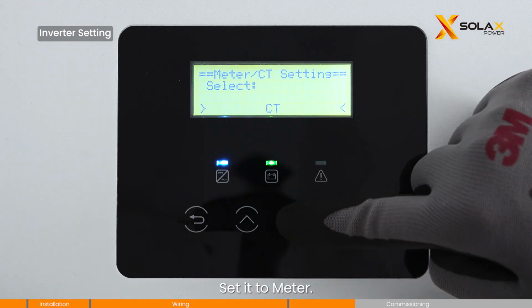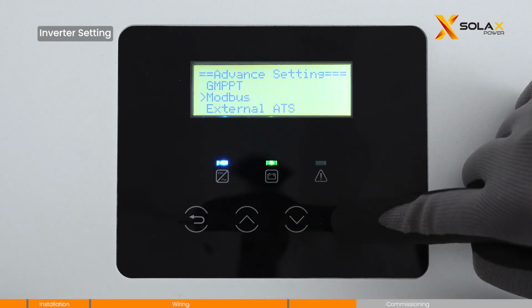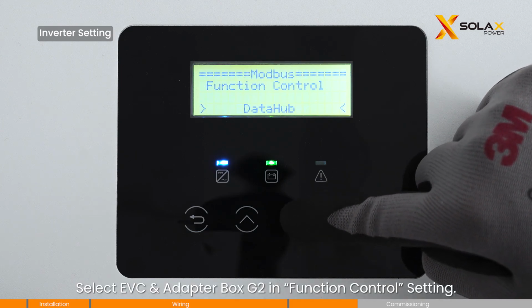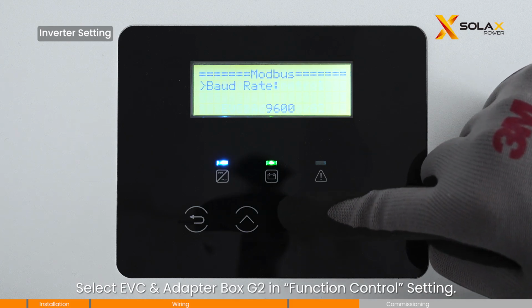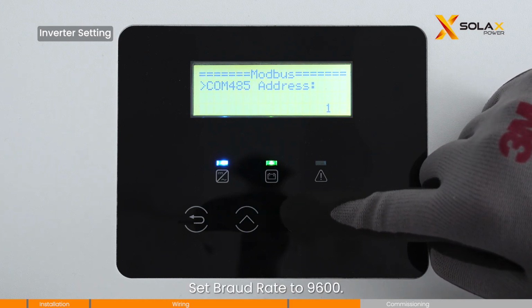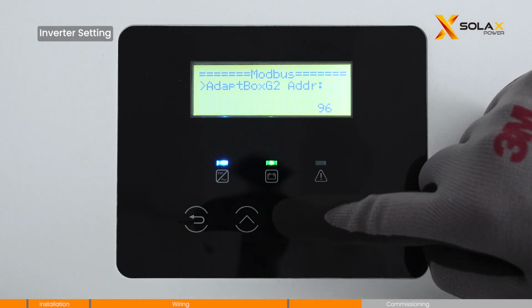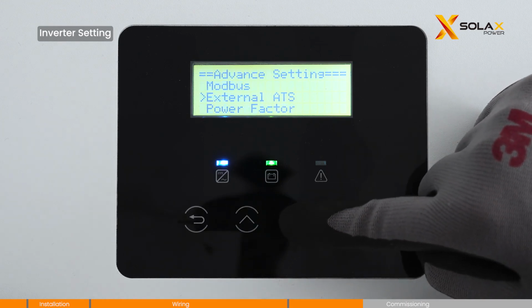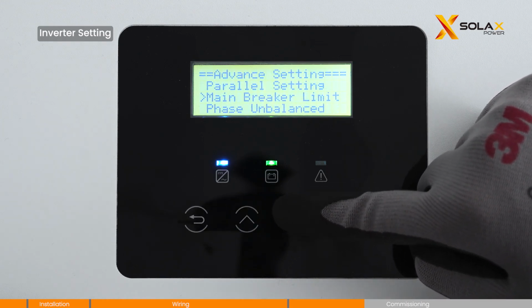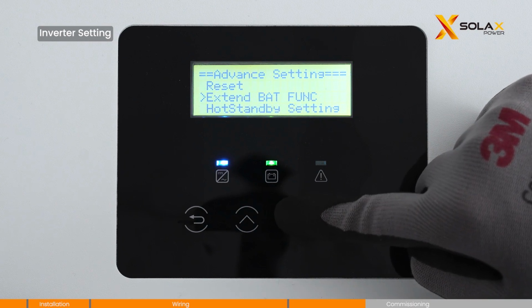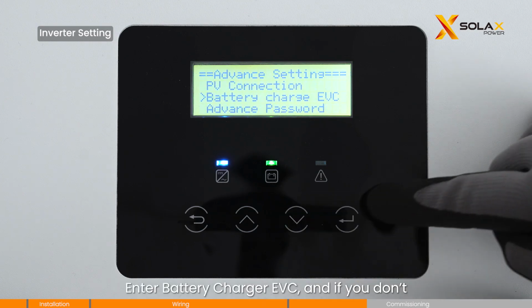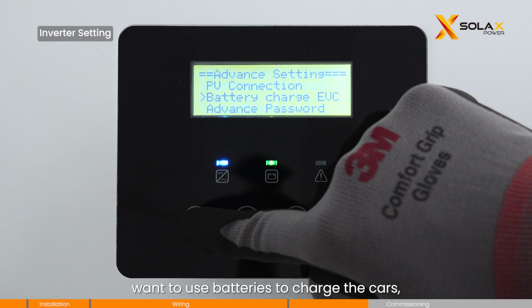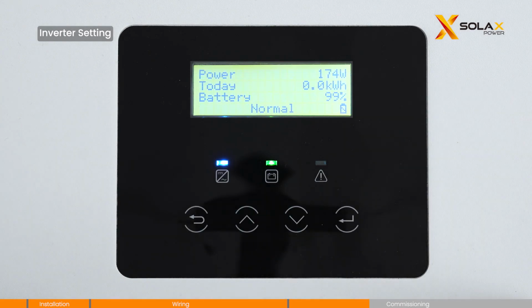Set it to meter. Select EVC and adapter box G2 in Function Controlled setting. Set baud rate to 9600. Enter battery charger EVC. If you don't want to use batteries to charge the cars, just set Disable.